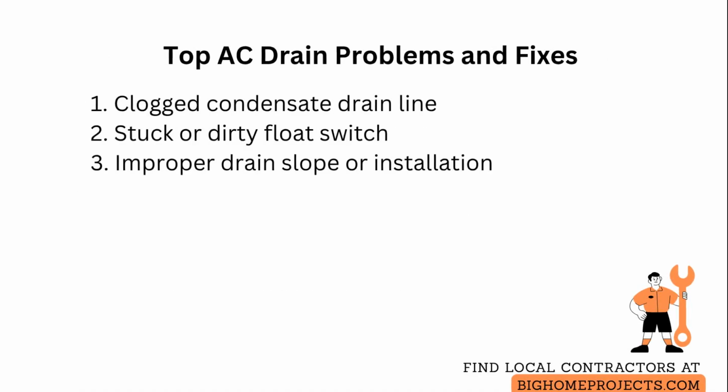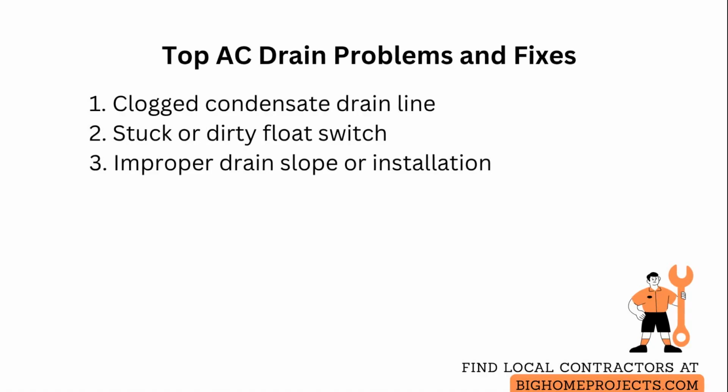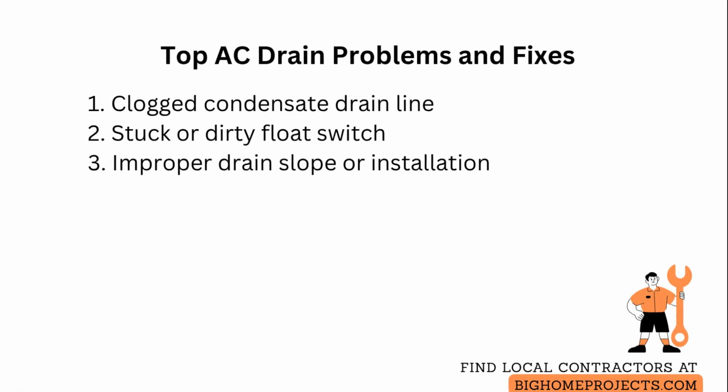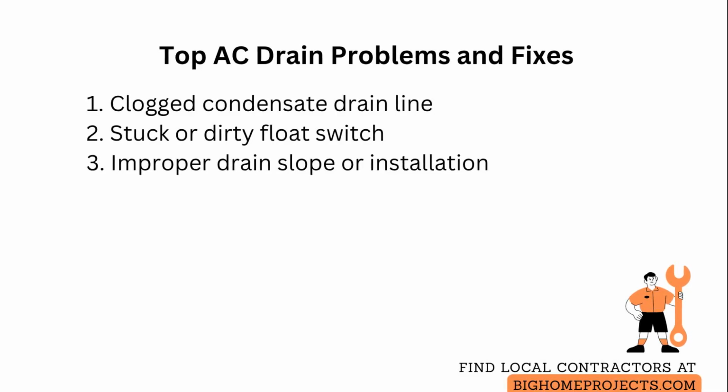The most common issue is a clogged drain line, which causes water to back up and trip the safety switch. Clear the line with a vinegar flush or wet vacuum and check for collapsed tubing, then retest the switch.